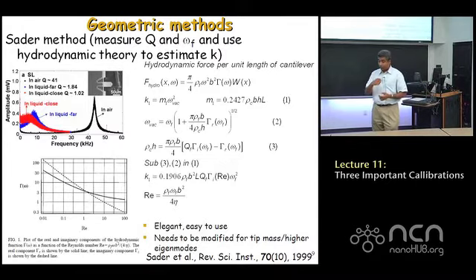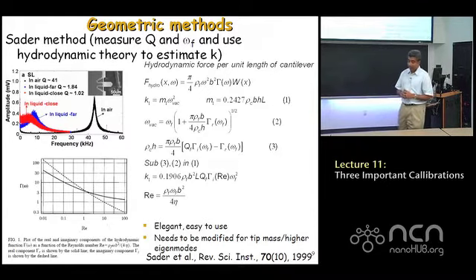There's a second component of force, which is called the added mass effect. What it means is, as you're trying to oscillate the cantilever, you're accelerating the surrounding fluid. There's a whole volume of fluid that you're carrying with you. So think of it like a skin. The cantilever isn't vibrating on its own. As the cantilever accelerates back and forth, you have to take into account the inertia of the surrounding fluid as well, which effectively adds mass, right? So the cantilever oscillating in water feels a lot more inertia than it does in air or in vacuum. So there are two components to this.